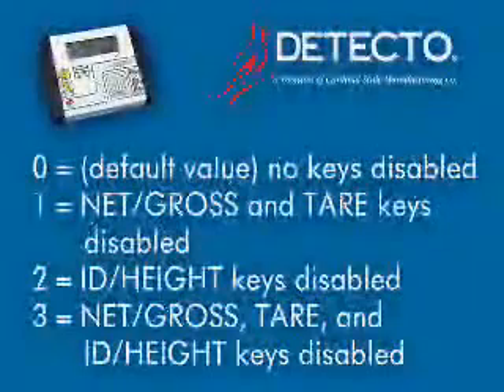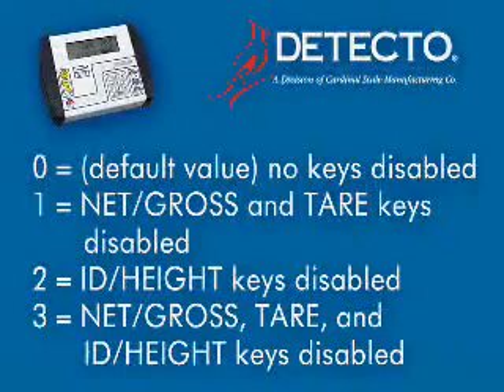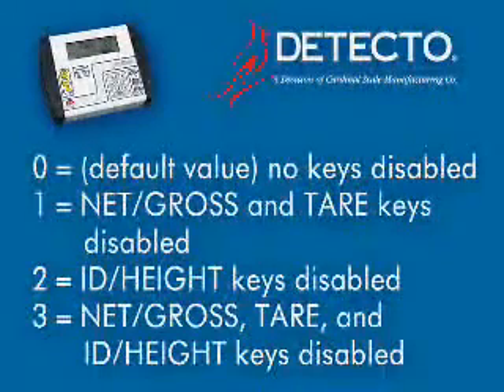The numeric values for disabled keys are: 0 for no keys disabled — this is the default value; 1 for Net, Gross, and Tare keys disabled; 2 for ID Height key disabled; 3 for Net, Gross, Tare, and ID Height keys disabled.